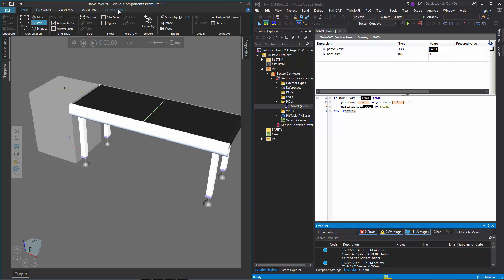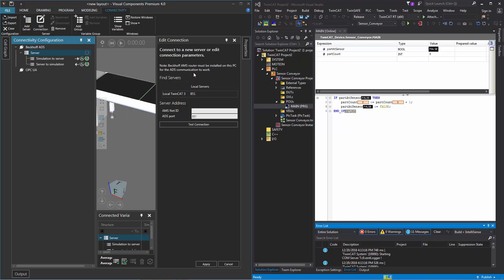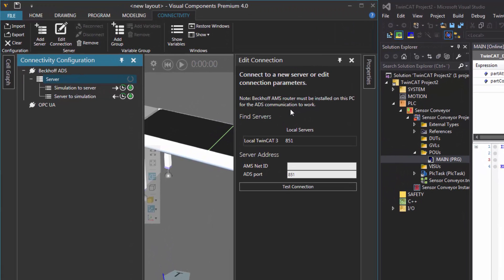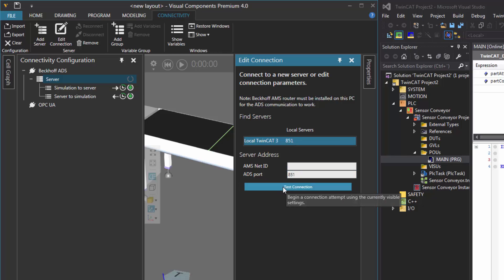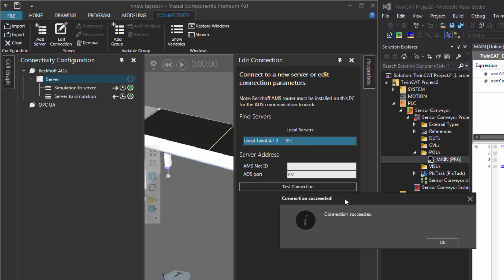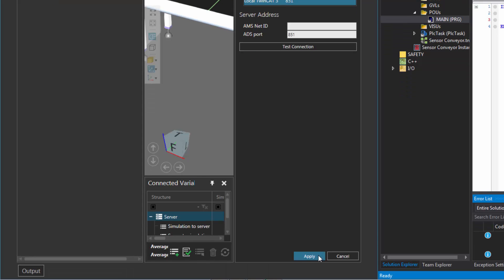To establish the connection, click the connectivity tab and then in the connectivity configuration panel, click Beckhoff ADS. In the server group, click add server — this will add a new connection. In the edit connection task pane, we have a discovery service for PLC that listens to common ports in TwinCAT. It found port 851 with a PLC running there, so I'll click it. I'll test the connection by clicking this button. The prompt lets me know I can successfully connect my Visual Components product to that PLC, so I'll click OK. To confirm and establish this connection, I'll click the apply button.